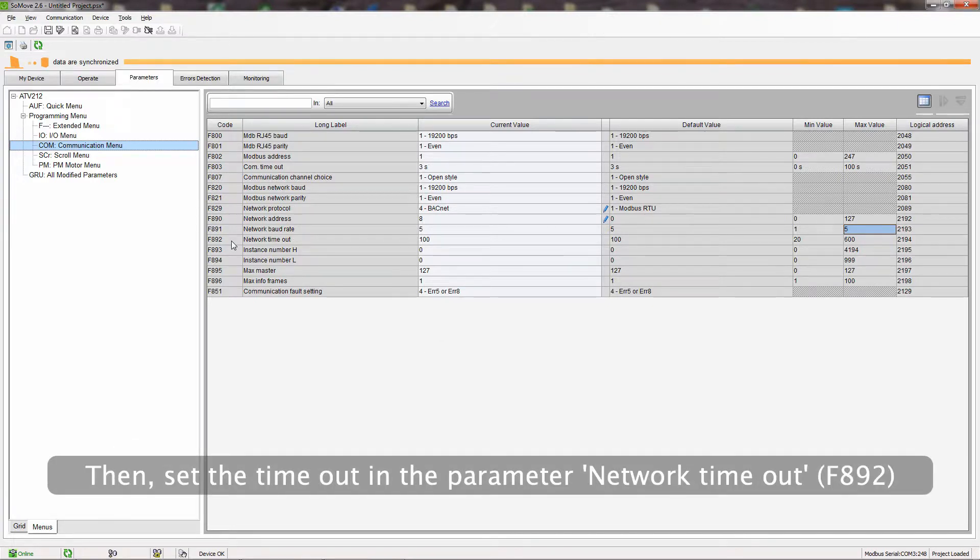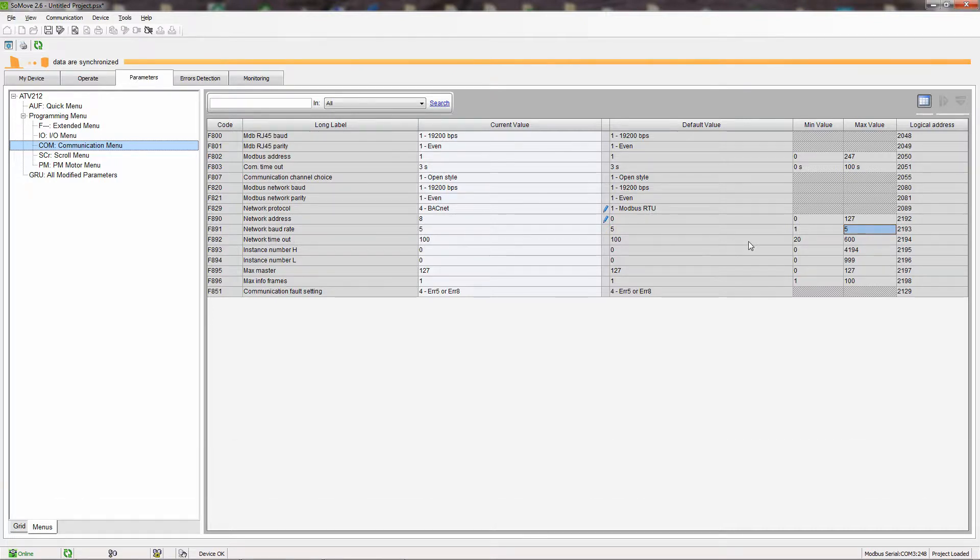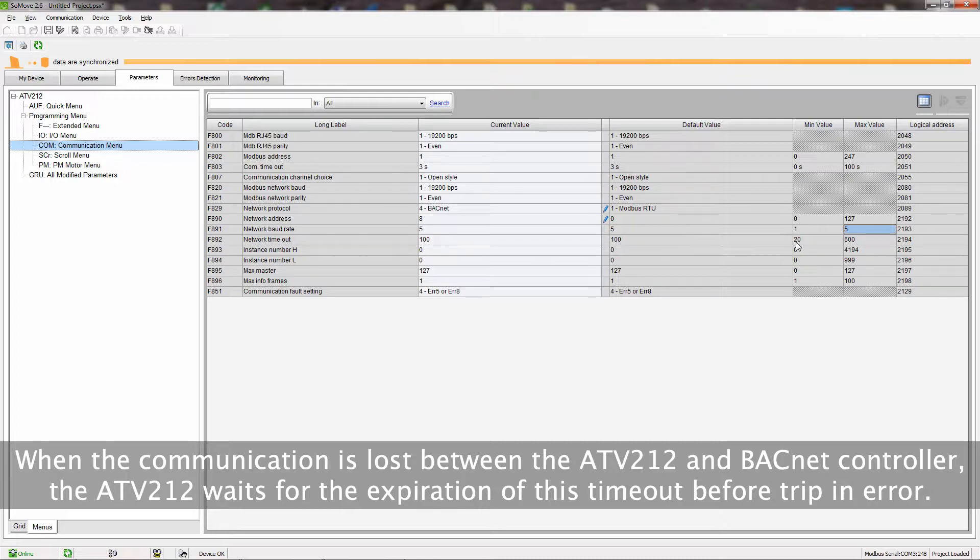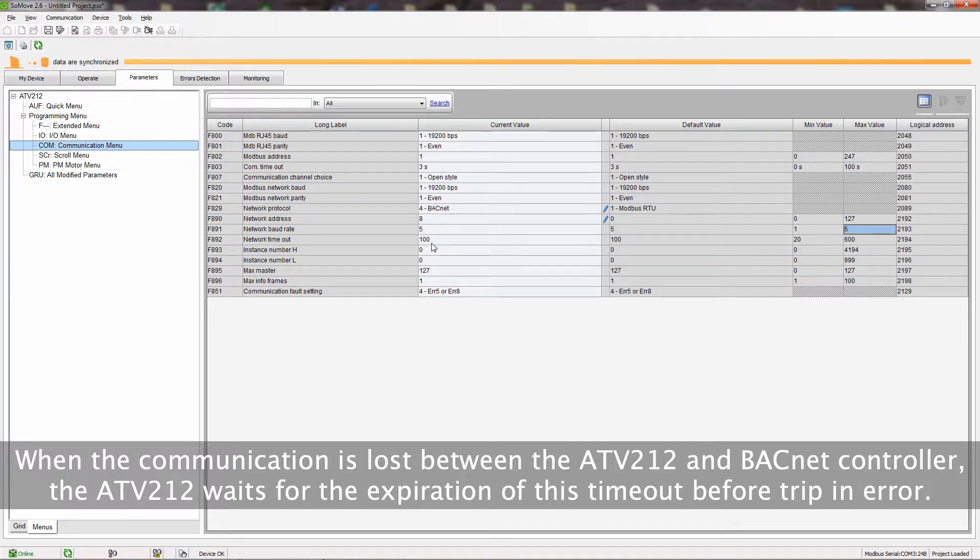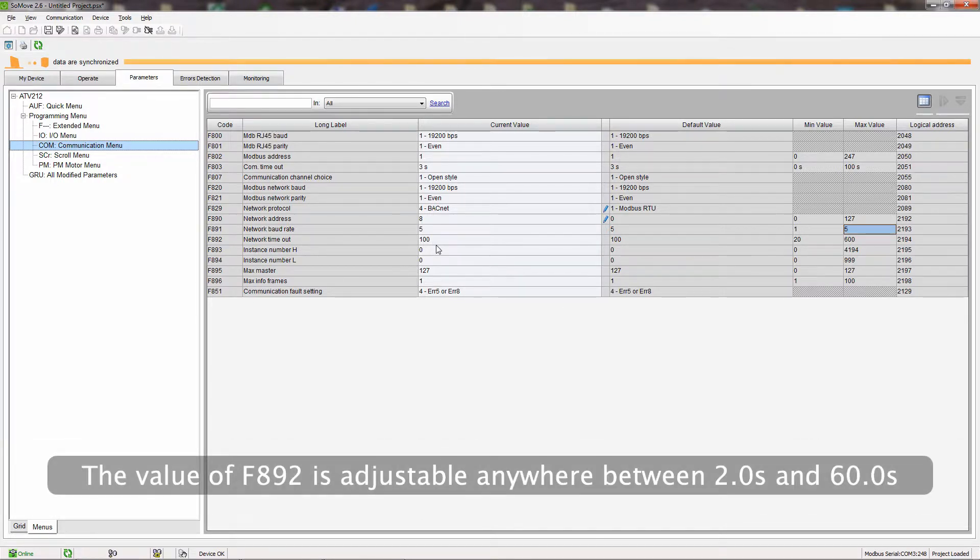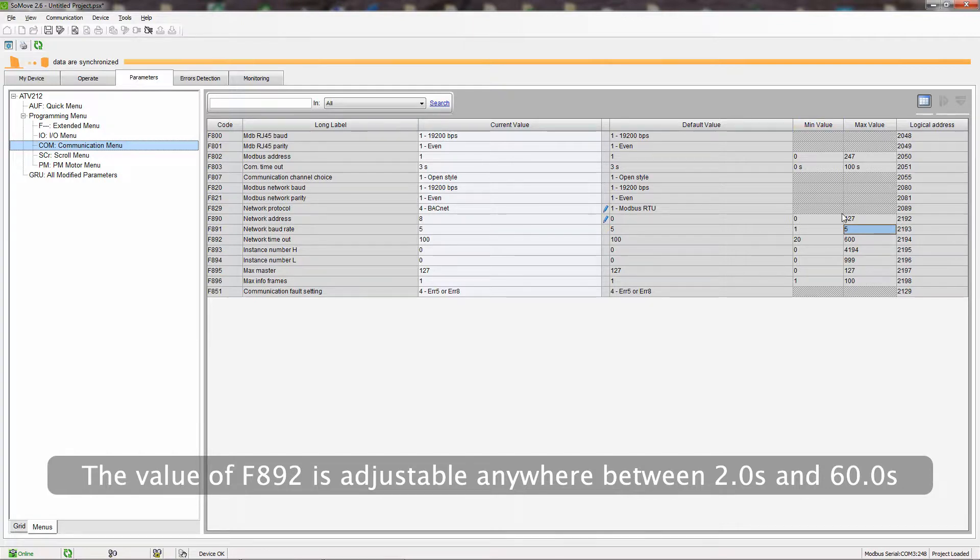Then set the timeout in the parameter Network Timeout. When the communication is lost between the ATV212 and BACnet controller, the ATV212 waits for the expiration of this timeout before trip-in error. The value of F892 is adjustable anywhere between 2.0 seconds and 60.0 seconds.